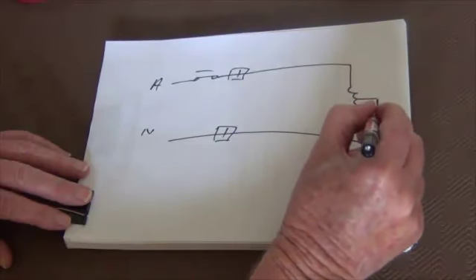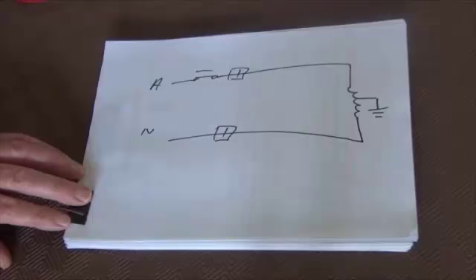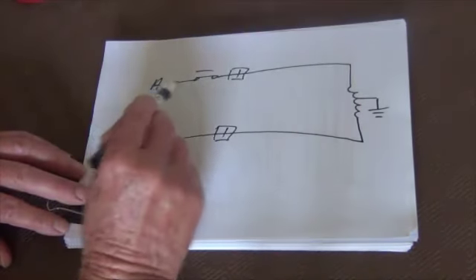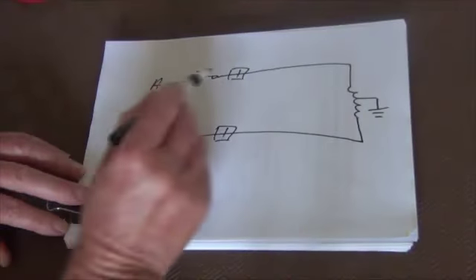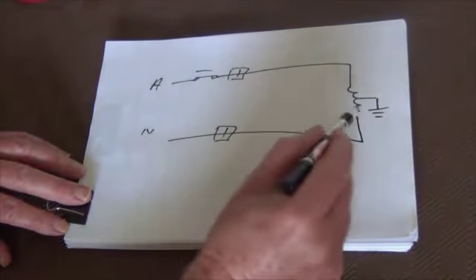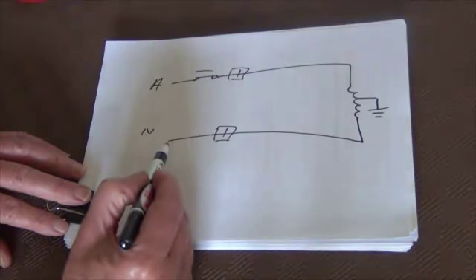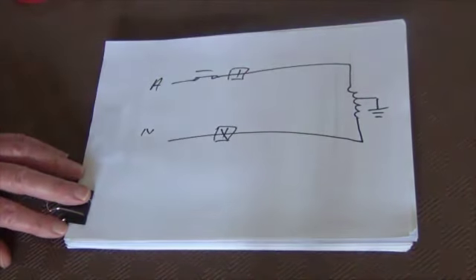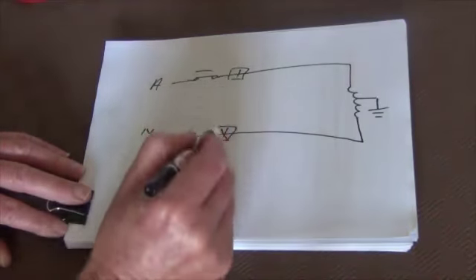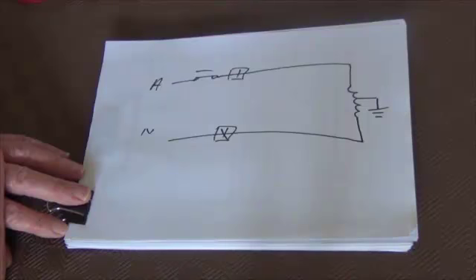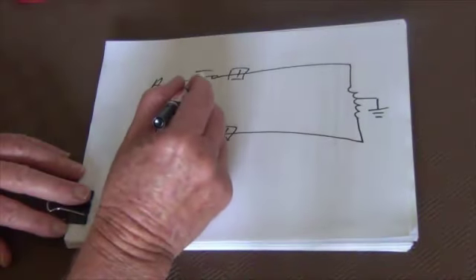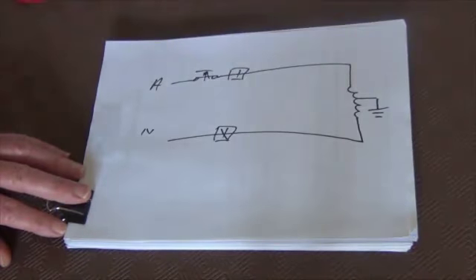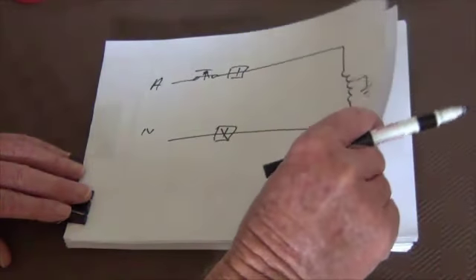But if this somehow went down to earth, say somebody touching the element and touching earth at the same time, the current flowing through here to that point would be different to the current flowing in this point. So therefore this meter would read differently, and somebody looking at the ammeters could think, oh dear, there's electricity going where it's not wanted to, and turn the switch off. Fairly simple principle. But we can't have somebody standing there watching the two meters all the time. So we do something differently.